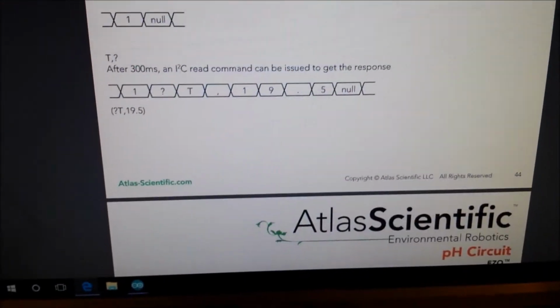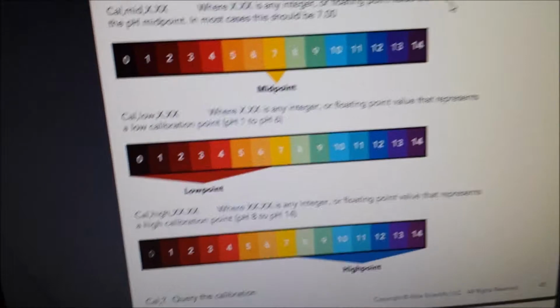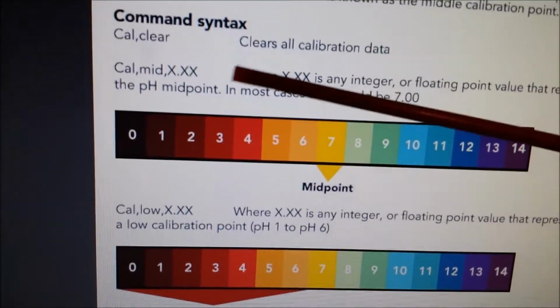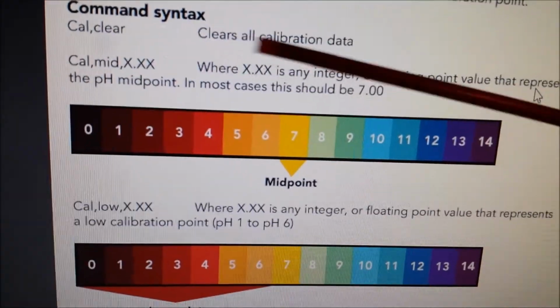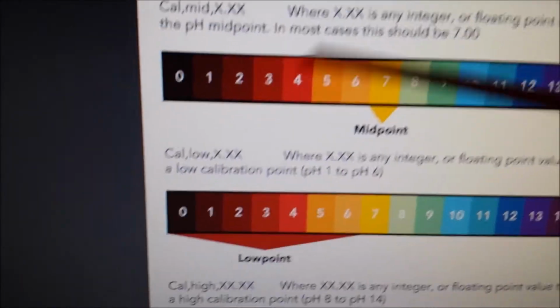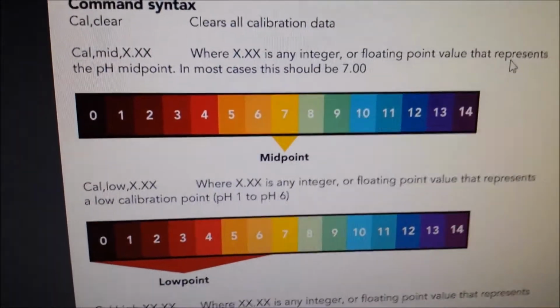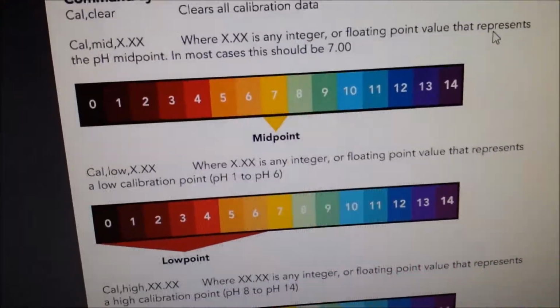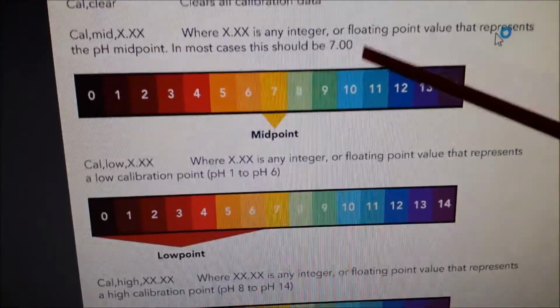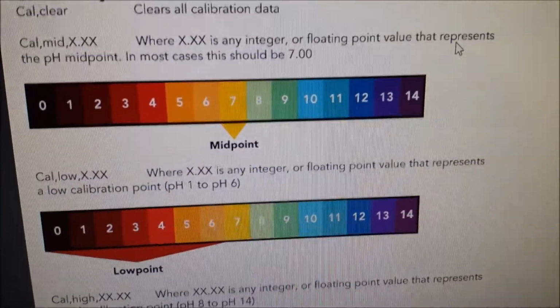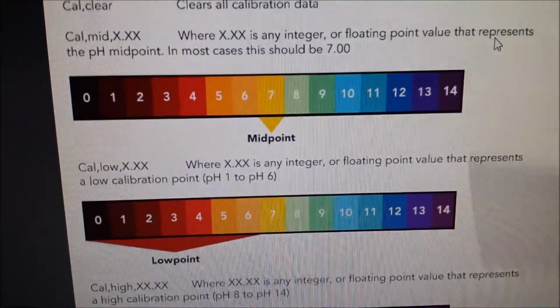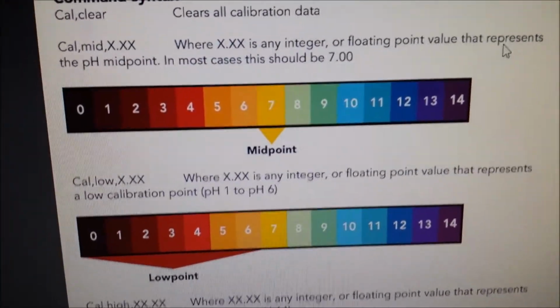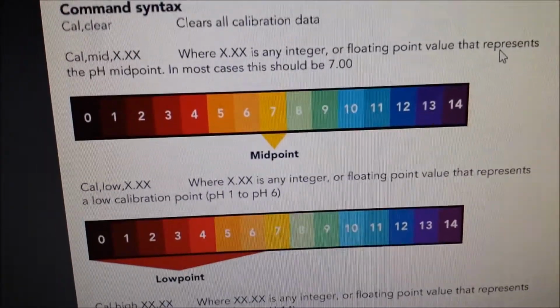Now, what we're going to do is if we scroll down to calibration here, these are the commands that we have to send. So you have to do cal, clear, that clears all the data, and then calibrate, mid, and then your pH. Now they recommend that pH 7.00 be your starting point. Now it could be 7.01 or 7.02. That's okay as long as it's a floating point value that represents the midpoint. And they recommend around pH of 7.